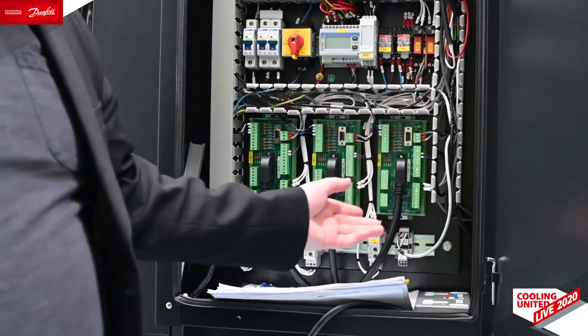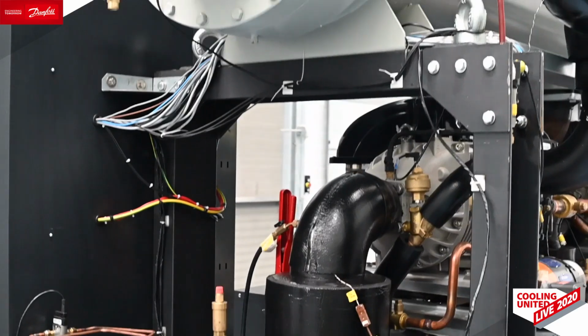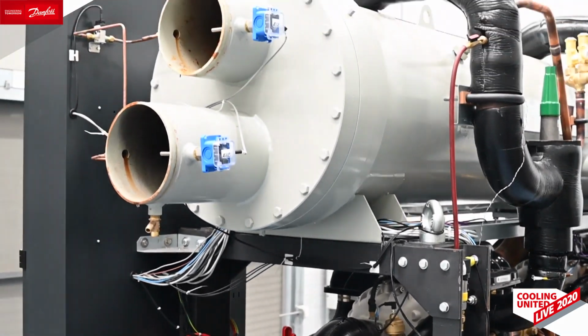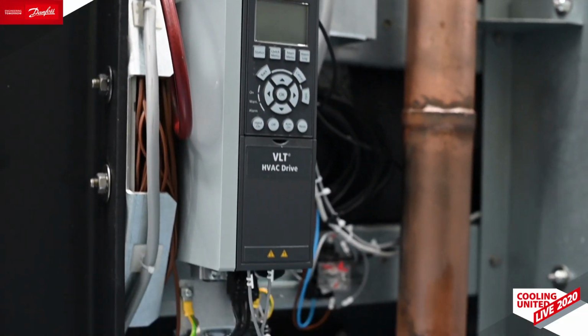During testing and development there were a lot of challenges to overcome. It's really a revolutionary unit because everything is variable - from the compressors to the expansion valve to the condenser bypass valve. These variable loops interfere with each other, so it becomes a constant balancing act to get the unit working correctly.